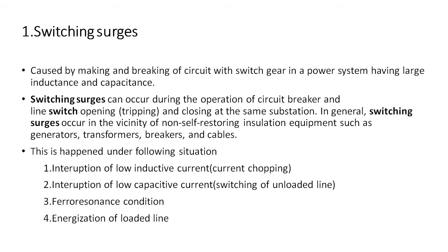Switching surges are caused by making and breaking of circuits with the switchgear in a power system having large inductance and capacitance. Switching surges can occur during the operation of circuit breaker and line switch opening, tripping and closing at the same substation. In general, switching surges occur in the vicinity of non-self-restoring insulation equipment such as generators, transformers, breakers and cables. This happens under the following situations. The first point, interruption of low inductive current, that is called current chopping. Second, interruption of low capacitance current, that is called switching of unloaded line. Third, ferroresonance condition. Fourth, energization of loaded line.